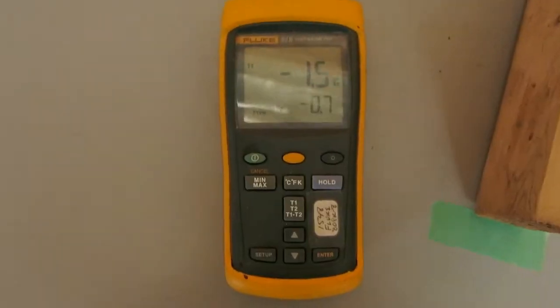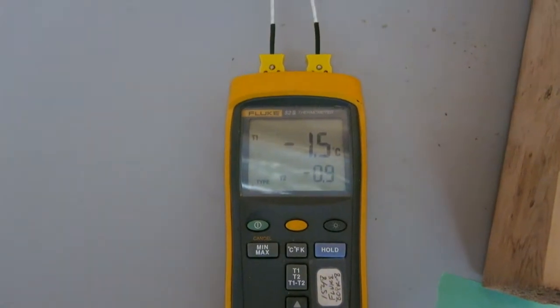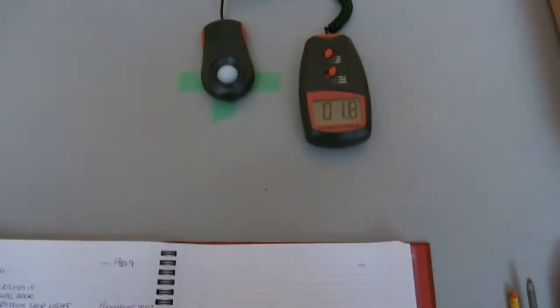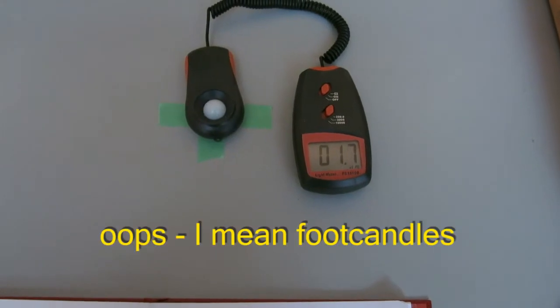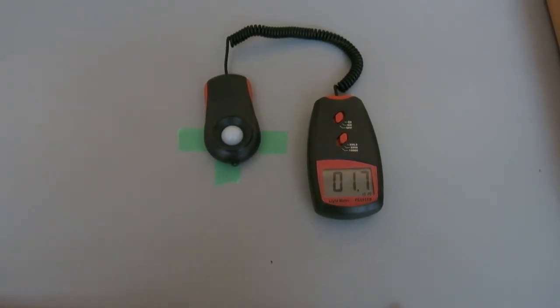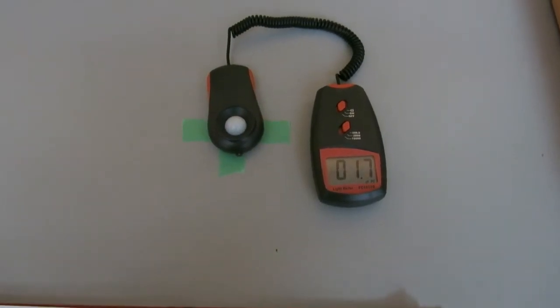The bottom reading — minus 0.8 — is the temperature of the room. The photometer is on, and normally I have a little bit of background; that's 1.8 footcandles. The sun is coming in through the window behind me and that's causing that. We would normally subtract that from whatever reading we get. Normally I do these tests when it's dark, like in the early morning.